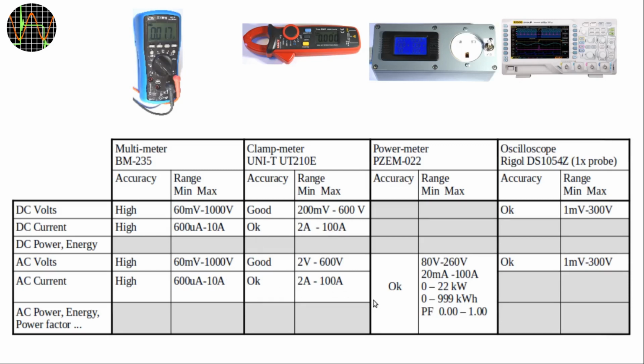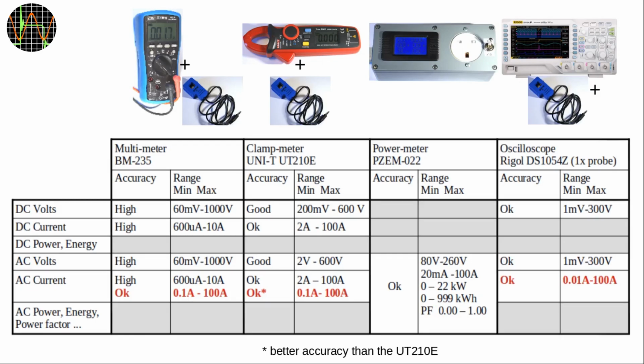The power meter is limited to AC mains, but in contrast to the other devices, it can measure voltage, current and phase angle simultaneously to calculate power and power factor and energy consumption. And of course the scope allows you to see the waveform, but only measures volts. Adding a current transformer expands the capability of each of these devices. It changes a simple multimeter to a clamp multimeter, allowing it to measure AC currents of up to 100 amps for an unlimited time without breaking the circuit.